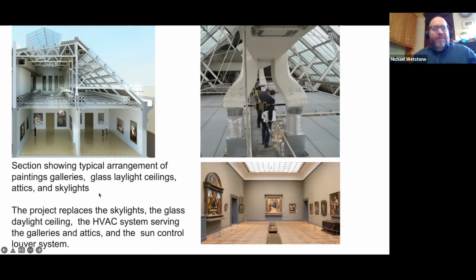One problem is that we have an antiquated skylight system of single glazing; the last one was installed in the 1930s, and we're trying to keep 70 degrees and 50% humidity in the galleries at all times. So there's an enormous problem, not only with heat loss through the single glazing, but with trying to prevent condensation. In winter, when the glass gets cold, water tends to form on it. So the museum previously had to heat the attics to more than 100 degrees all winter long, so condensation wouldn't form, at an enormous loss of energy and heat. In addition, the HVAC systems were overtaxed, and sometimes the steam reheat coils would spring leaks, making it a complicated problem calling for a comprehensive solution.